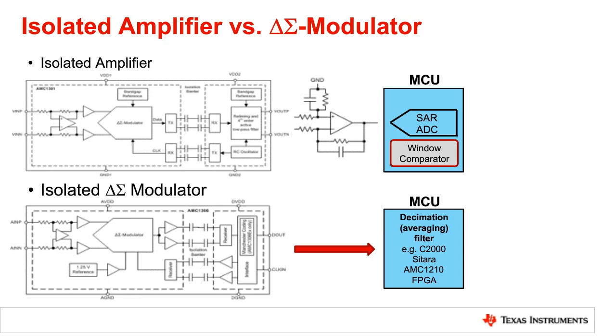On the low side of the isolation barrier, you can see that there's a fourth order filter and an oscillator, which is going to generate a clock that will feed a delta sigma modulator on the high side, and then the data output is passed into the fourth order filter. The output of this system can be passed through a simple differential amplifier and into the SAR ADC on a typical MCU or MPU used in your DSP calculations.